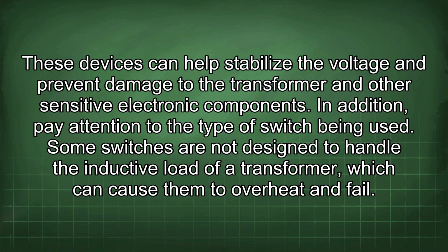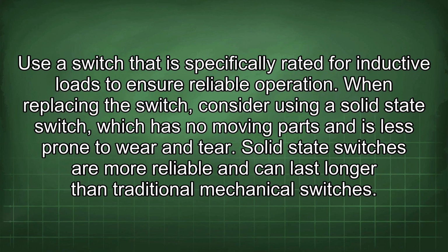In addition, pay attention to the type of switch being used. Some switches are not designed to handle the inductive load of a transformer, which can cause them to overheat and fail. Use a switch that is specifically rated for inductive loads to ensure reliable operation. When replacing the switch, consider using a solid-state switch, which has no moving parts and is less prone to wear and tear. Solid-state switches are more reliable and can last longer than traditional mechanical switches.